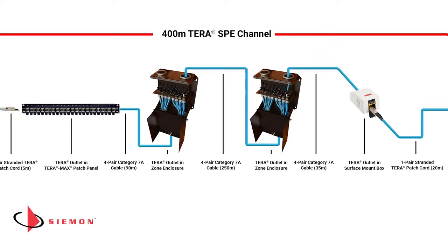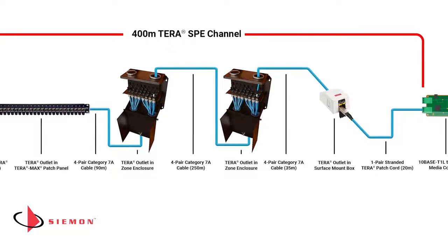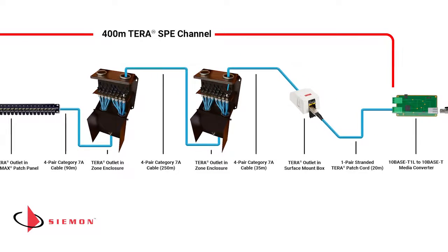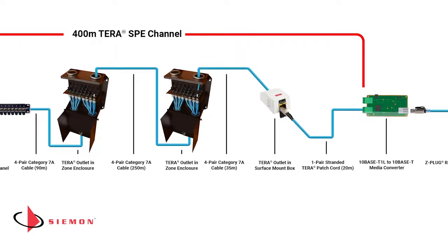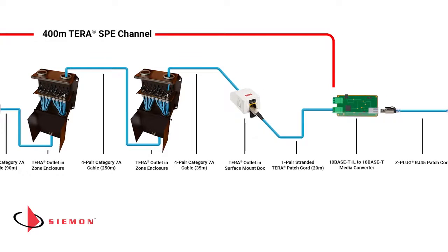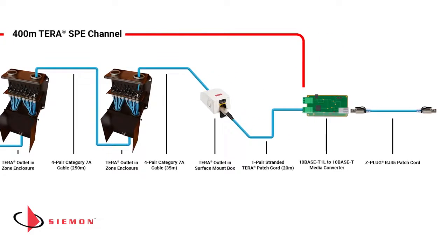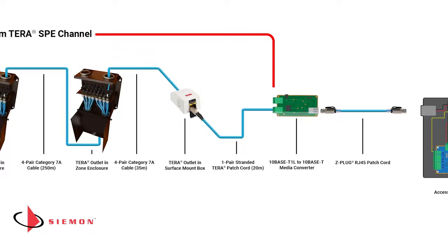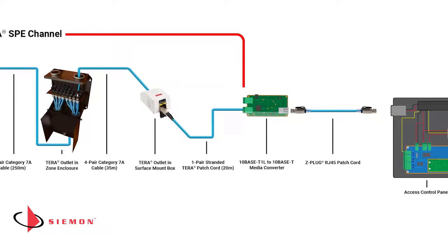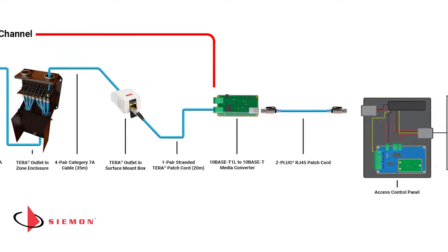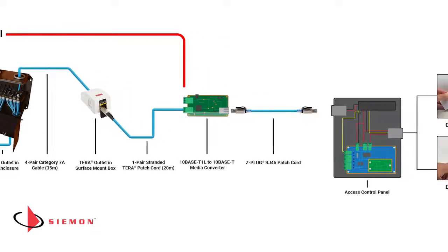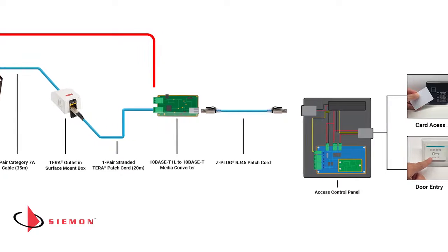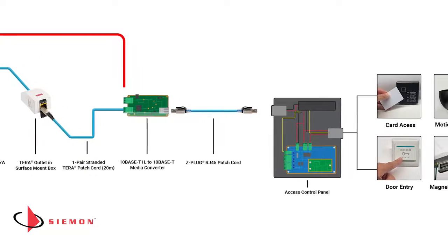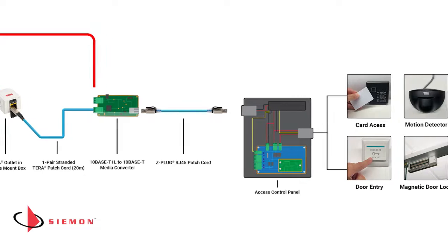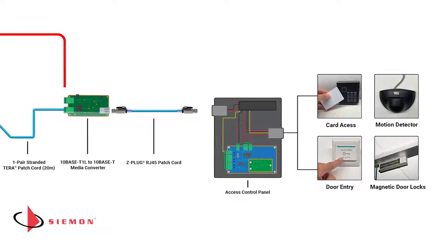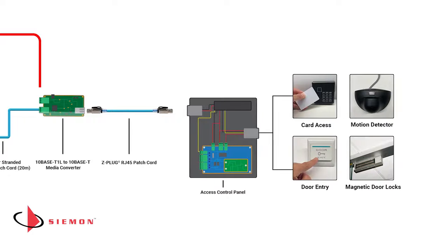The outlet in the first zone enclosure is connected to a TERA outlet in a second zone enclosure by 250 meters of solid cable. 35 meters of solid cable then extends from the second zone enclosure to a TERA equipment outlet. And finally, a single-ended one-pair TERA cord connects the far end of the SPE channel to a second media converter that transitions the signal back to TCP/IP for connection to the locally powered security access controller box. Our end devices are connected to the controller box with manufacturer recommended control cables.